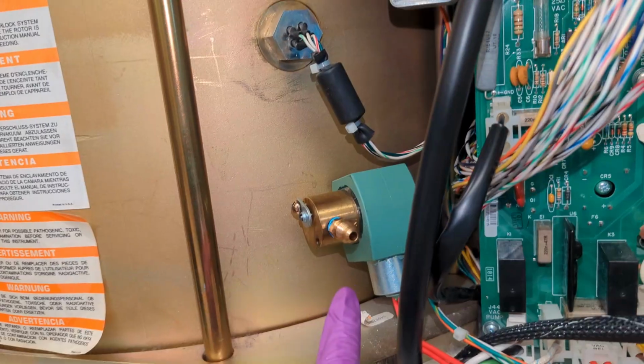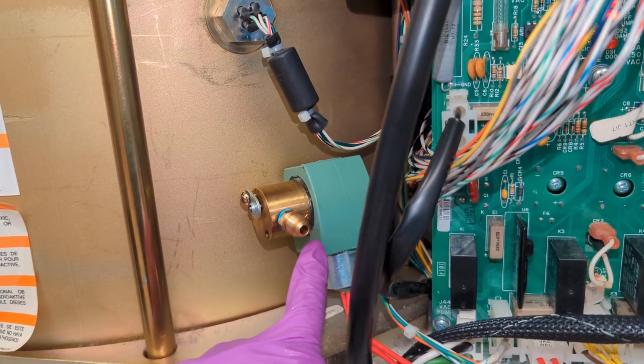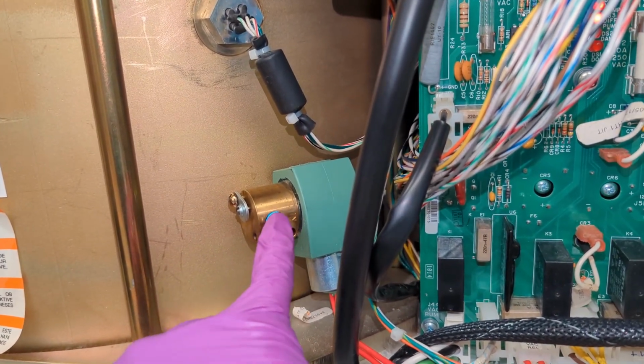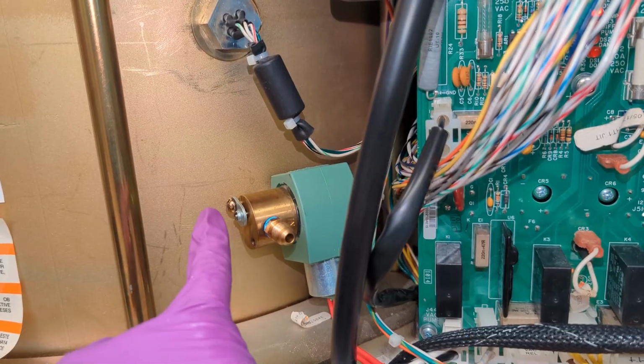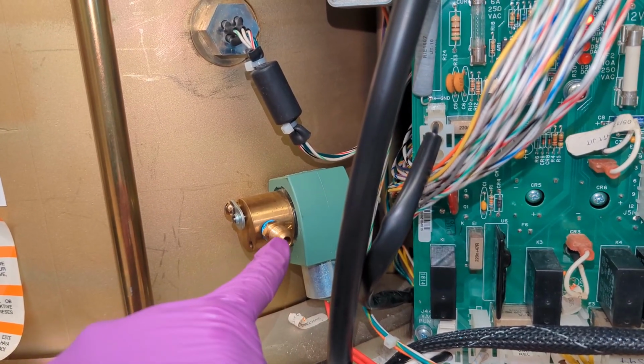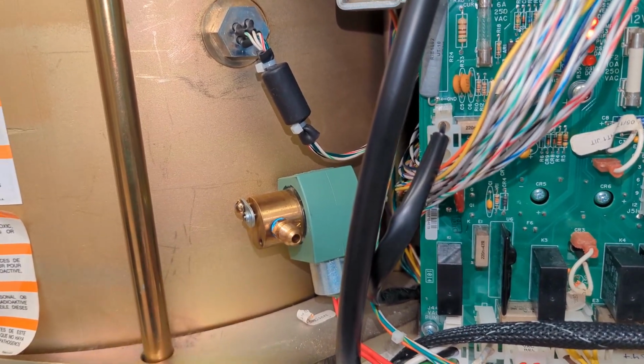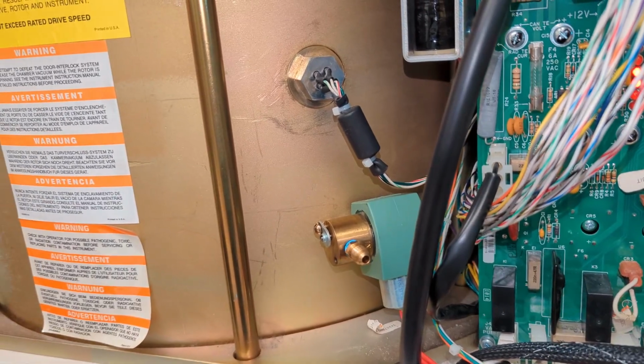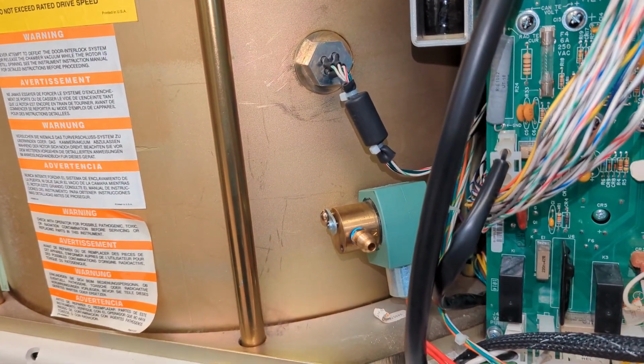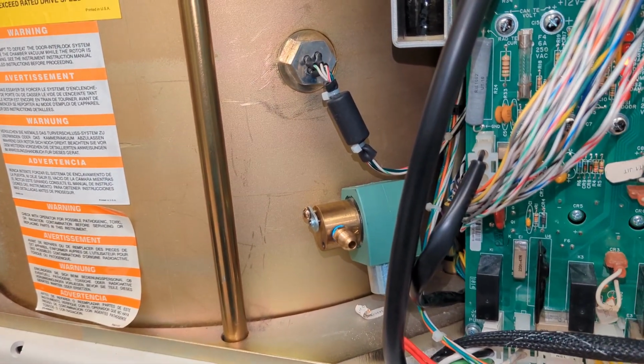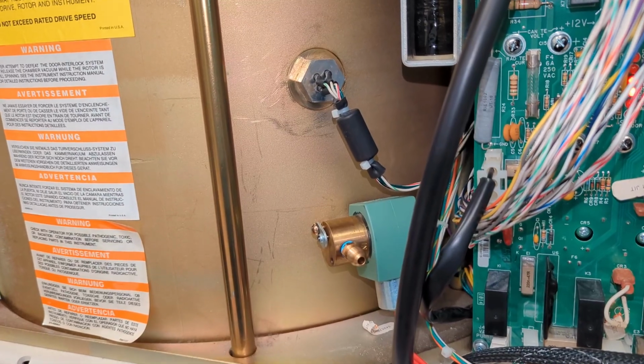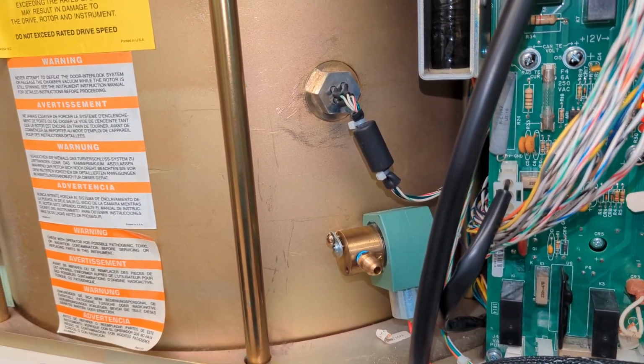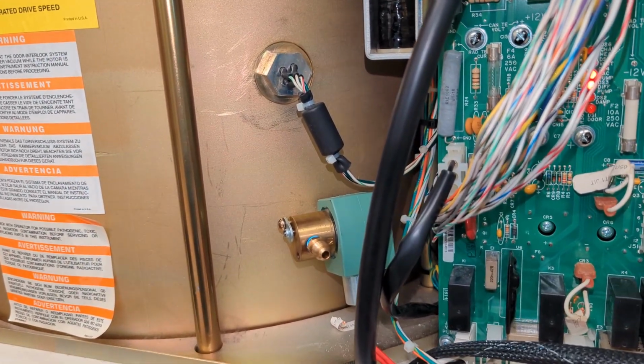So yes, there could be a leak going on, but also you can see you've got this solenoid, this vent solenoid, and I decided to hook up a gauge to this and manually open it, and with the vacuum running, I can measure a vacuum as low as 4 microns. So I'm wondering if this could be a calibration problem.